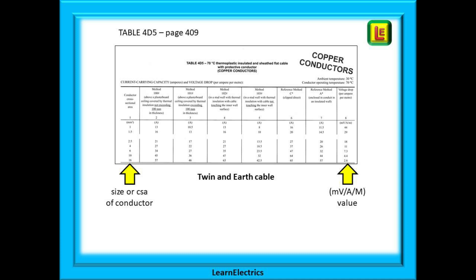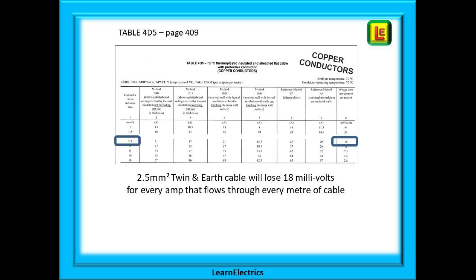Turn to page 409 in the wiring regulations and we will find table 4D5. The leftmost column lists the size or CSA of the conductors, and the rightmost column lists the mV/A/m number for each conductor size. Find 2.5 millimeter conductor size in the leftmost column and then trace along the row to the far right column where we will find the number 18 in this case. This is the mV/A/m number for 2.5 millimeter twin and earth cable. This size cable, 2.5 millimeters, will lose 18 millivolts into the cable for every amp of current that flows and for every meter length of the cable.